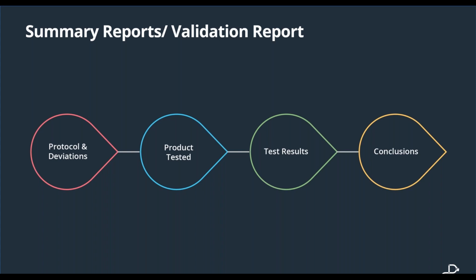So your usability engineering report should be discussing your safety related considerations, any issues you found, processes, resolutions, and any conclusions that you've made. And that level of detail in that documentation should be enough to describe your identification, your evaluation, and the final assessment of all serious use-related hazards for the device.